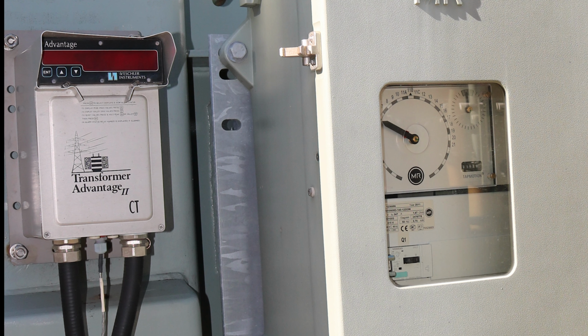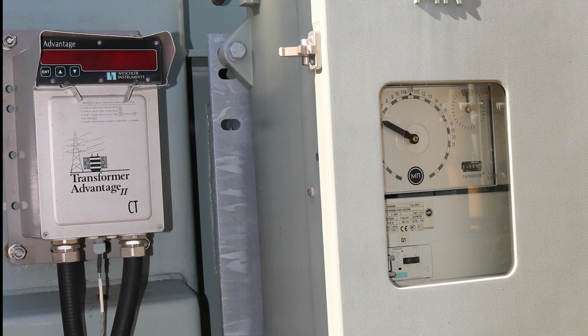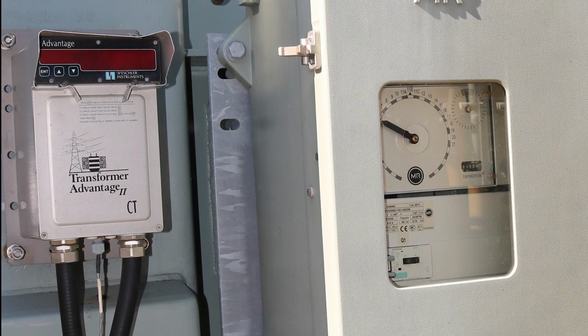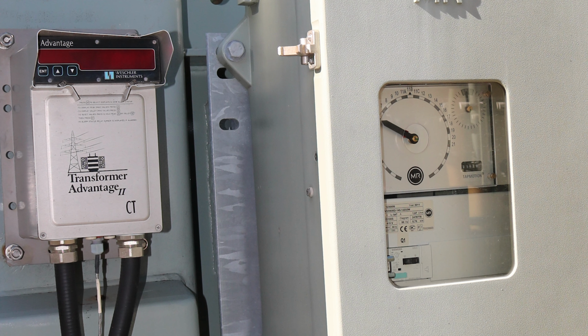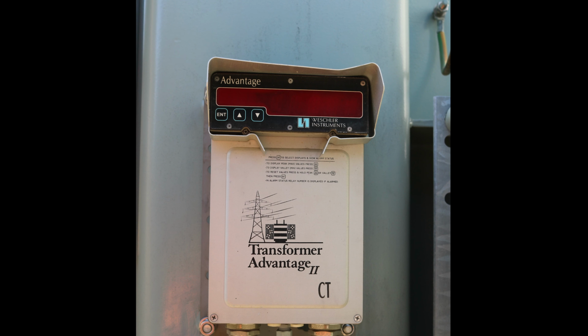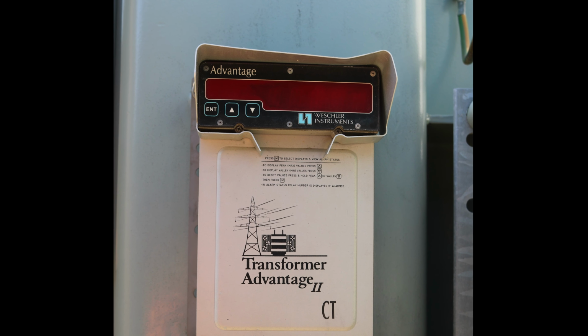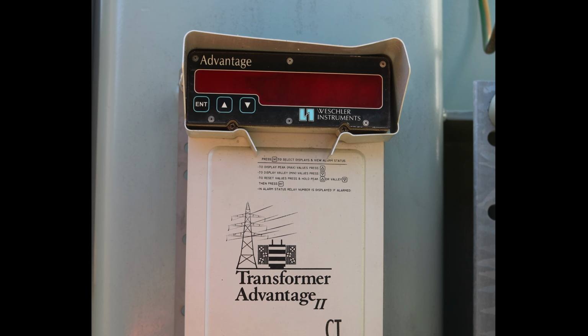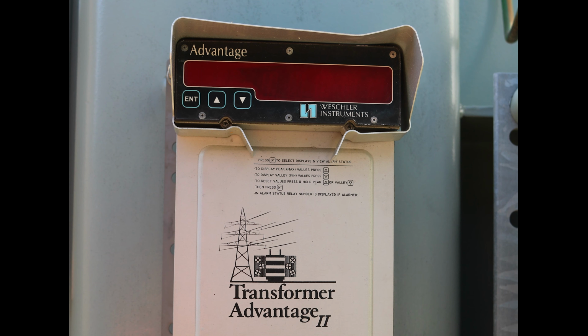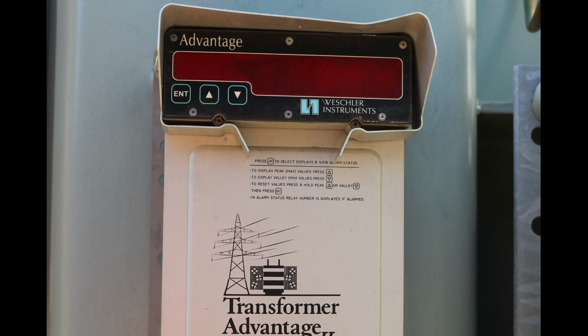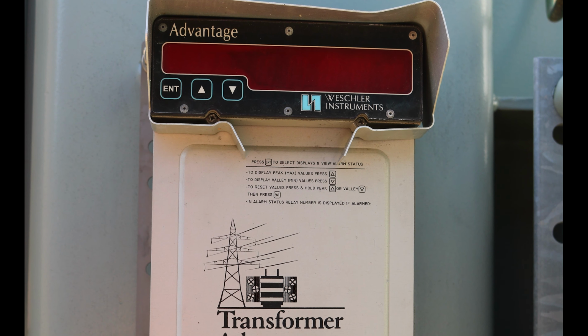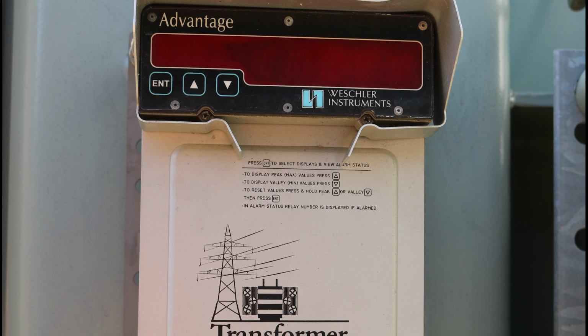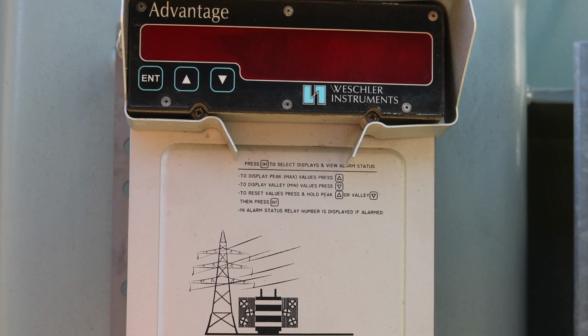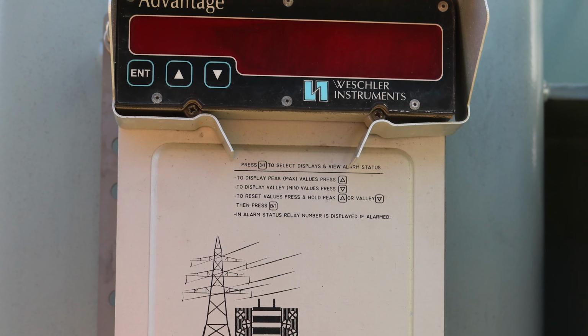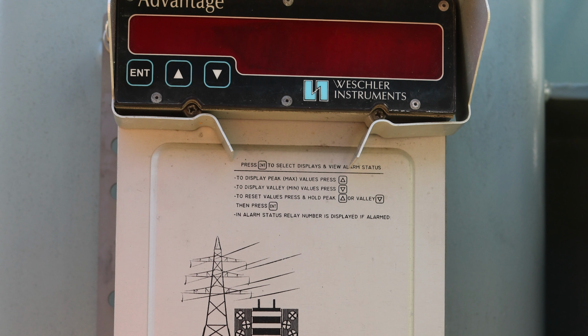So oil temperature and winding temperature is a really important part of protecting a transformer, and the way we monitor that is with this system here. So this is an instrument that's dedicated to monitoring the oil temperature and the winding temperature. There is a CT in this box which will send a signal to the transformer protection scheme if the oil temperature or the winding temperature get above preset thresholds. If the transformer is getting too hot, it's either because it's been overloaded or there's some kind of internal fault in the transformer that's creating heat in the oil. If that happens, this system operates and will send a trip signal to the circuit breaker.